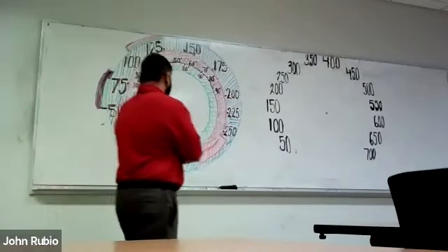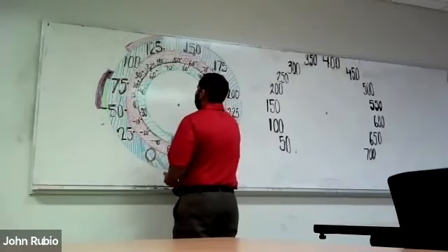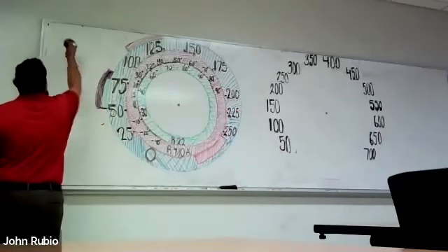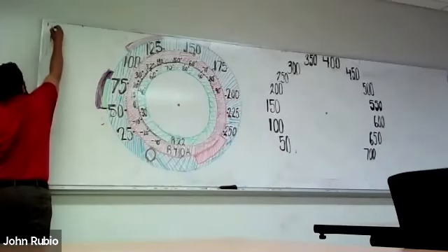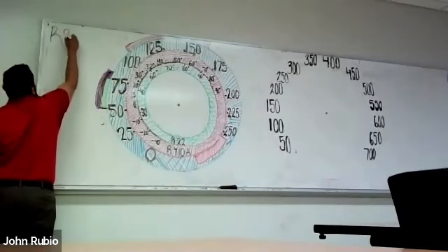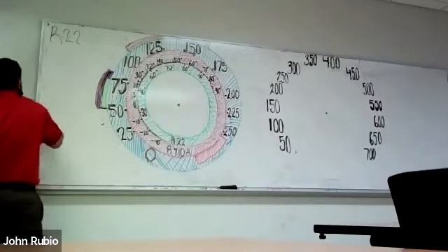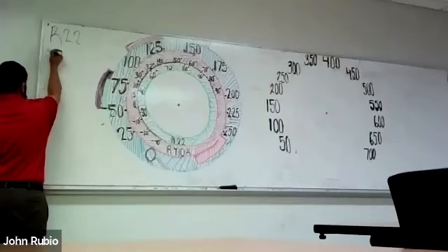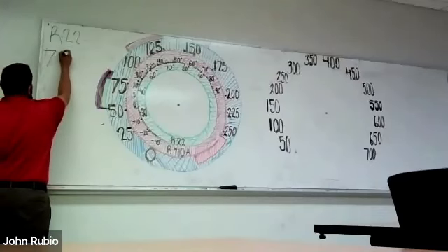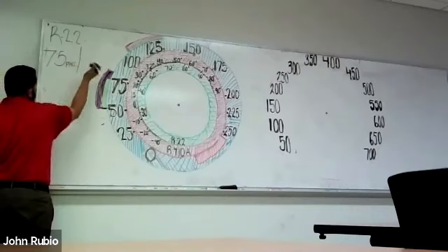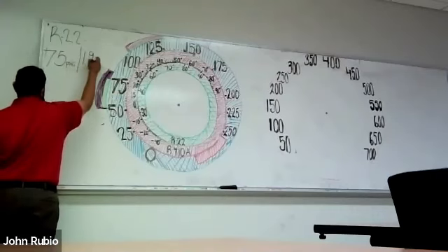So we're going to start with the R22, and we're going to touch on what we covered yesterday. When we're talking about R22, we're going to go straight for operating pressures. We learned that typical operating pressures for R22 are 75 psig over about 195 psig.